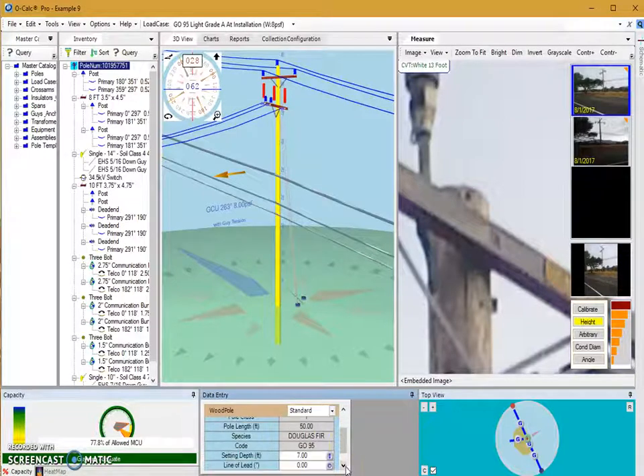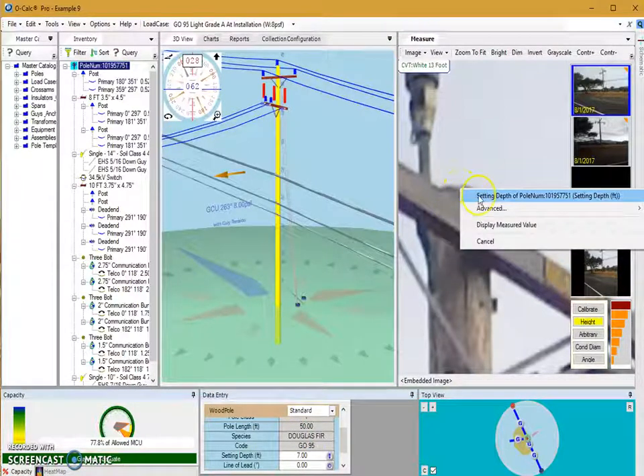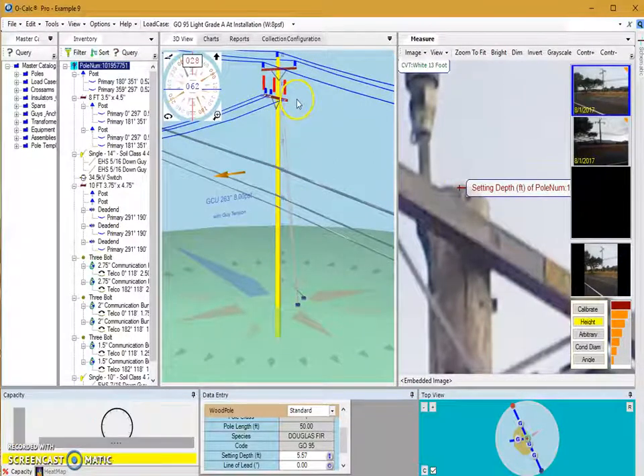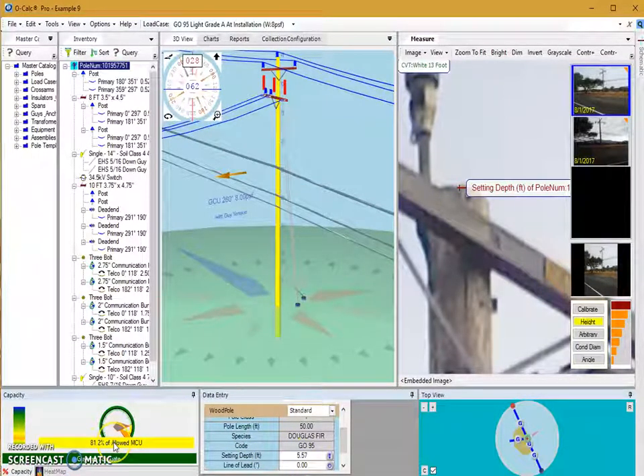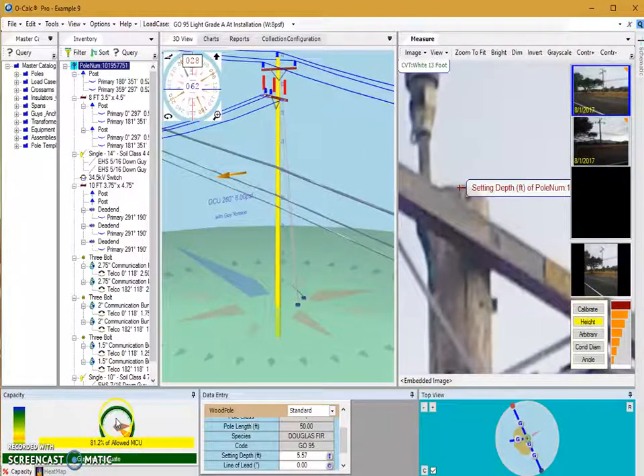My current setting depth is set to seven feet. I'm going to left click at the top of the pole to change it — I'll see that my pole actually came up a little bit and our setting depth changed to 5.57 feet. Our capacity changed accordingly from 77% to 81.2%, so you'll see that in cases where you're close to the capacity being overloaded, that can make a difference.